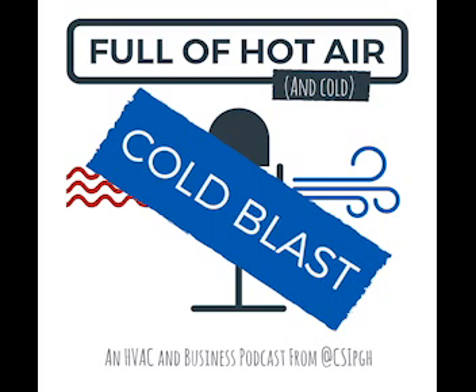Today I thought we'd start with a Mitsubishi product, any of the Mitsubishi products in the M&P Mr. Slim line. They use a specific type of wiring, and the wiring is actually kind of unique because it uses high voltage and also DC communicating voltage to pass between the outdoor unit and the indoor unit. And when there's a communication error, I get a lot of calls from techs like, where do I start? How do I know what's causing this communication error? So I have some pretty easy steps to break it down pretty quickly to where you should be focusing your attention when you get this type of error.